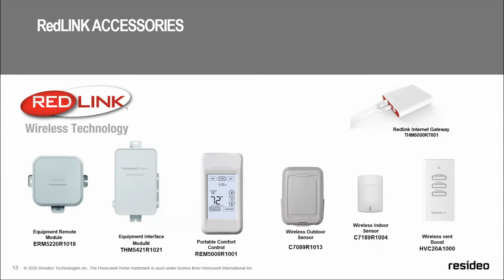The portable comfort control is a really nifty device in that it's almost like carrying a thermostat in your pocket. You want to move to a room that traditionally gets cold or hot and you don't use very often, go ahead and take it with you, and you can basically make that your point of control. The wireless outdoor sensor is used for things like dual fuel and bringing in that outdoor temperature set point. Take note on this one here: the wireless outdoor sensor is good for up to 16 thermostats. So you won't need to put an outdoor sensor on every one if you've got multiple in the house or building, particularly when you're doing zoning. The wireless indoor sensor, the C7189R, can be good, and in the RedLINK system, you can add up to six of those. And then we have some other accessories listed here, like the wireless vent boost and entry exit, some things that are more niche type products, but we do have a lot that can go on there.